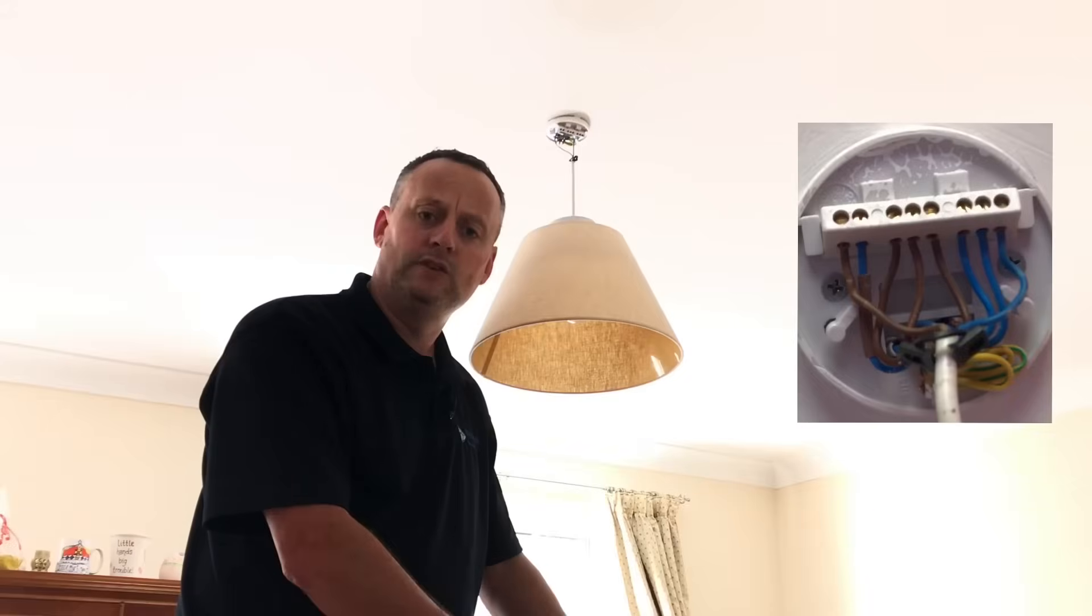We also got to see that twin brown wasn't being used as we're using twin brown in my workshop. They had to use twin and CPC. It wasn't a blue neutral returning from the switch, it was actually a switching line and we can see how the electrician this installation identified that with brown sleeving.